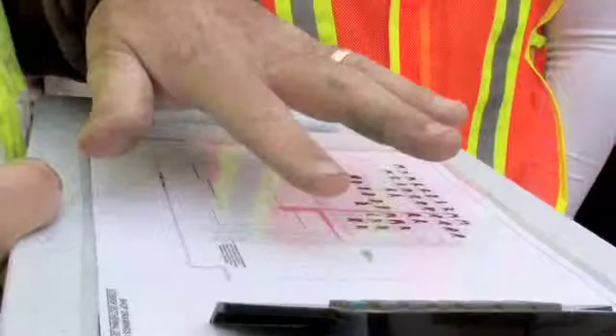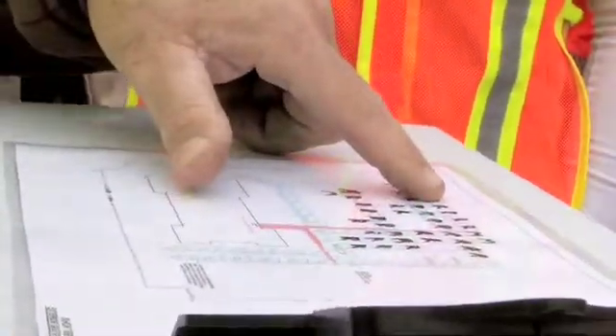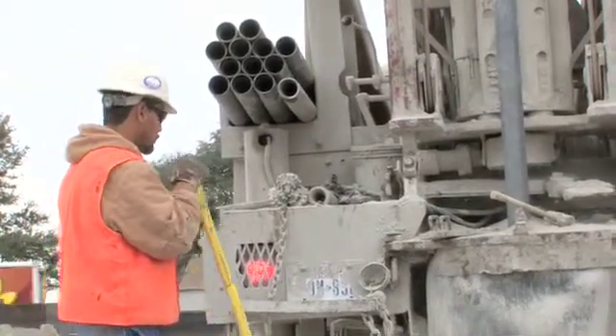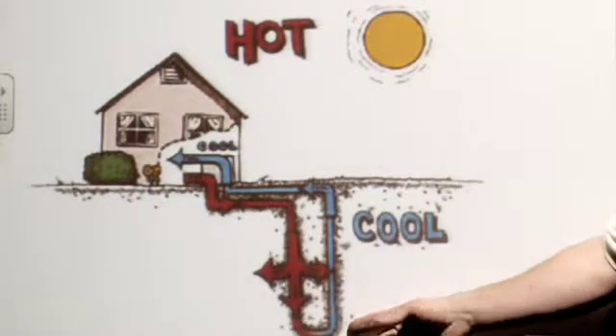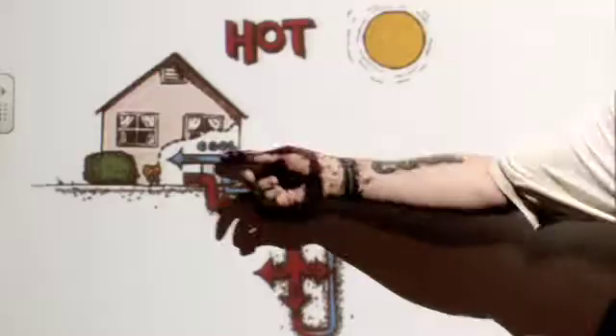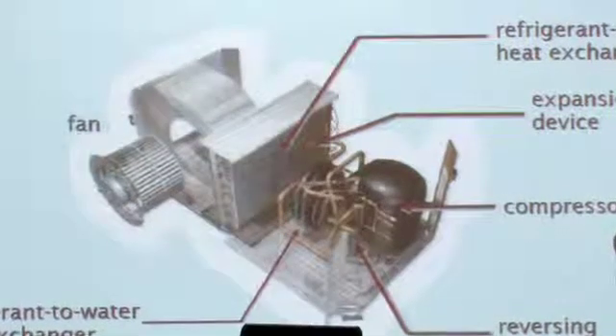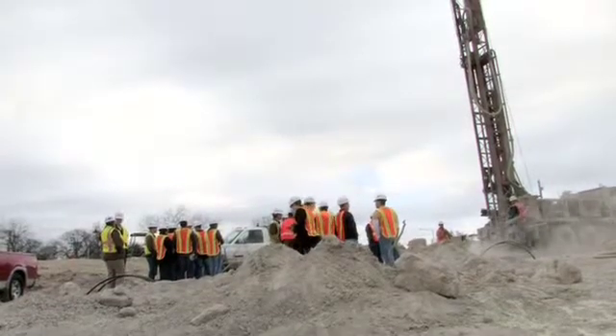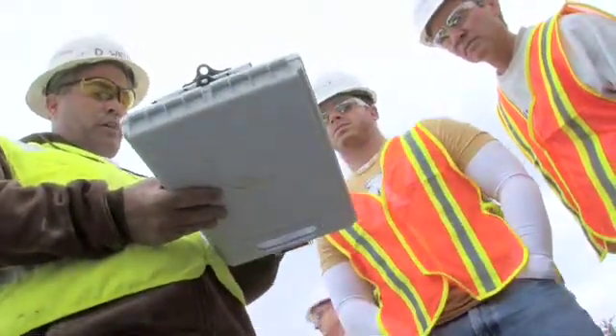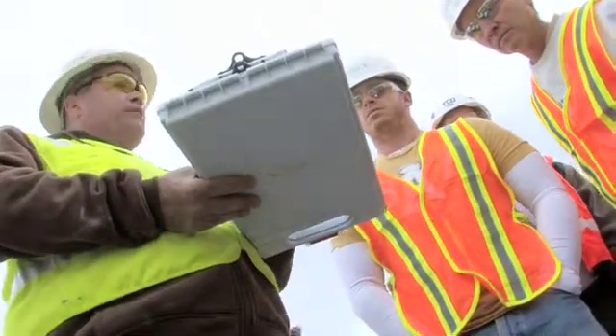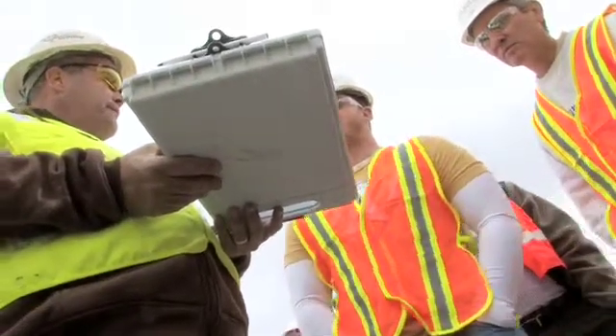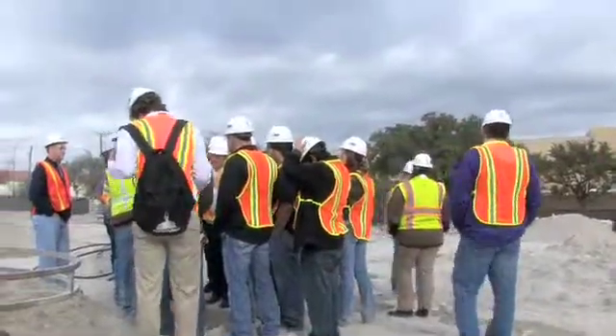The beauty of a system like this in this application is — number one — you've got TCU outstanding maintenance folks, so you've got people watching the systems. Also, the heat of the earth is used as your sink or your source. For example, in the summertime, with outside air conditioning systems, you hear your units running and feel the heat from the condensing unit — that's a transfer of heat to the air. But in Texas, the air can be 100, 105 degrees. If you could transfer that heat energy you're taking out of your building to the ground, which is at like 80 or 70 degrees, your systems are much more efficient.